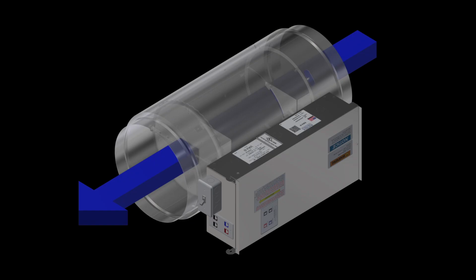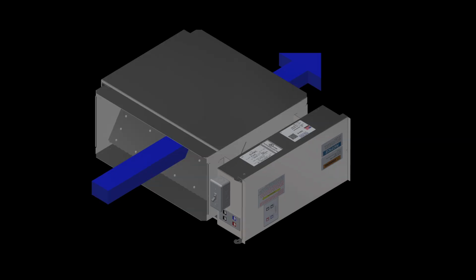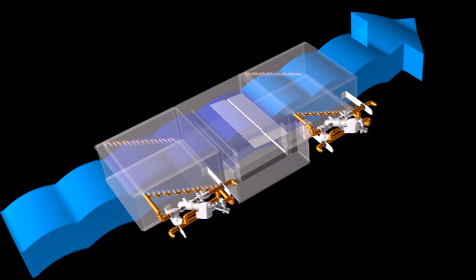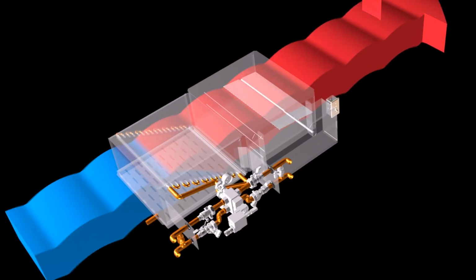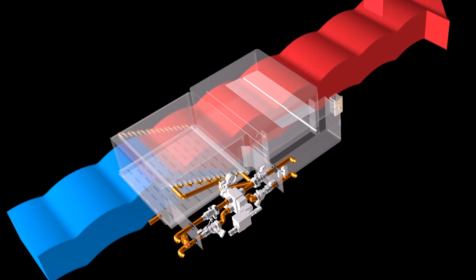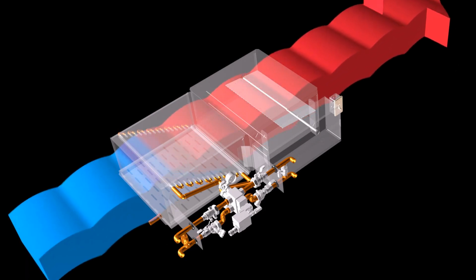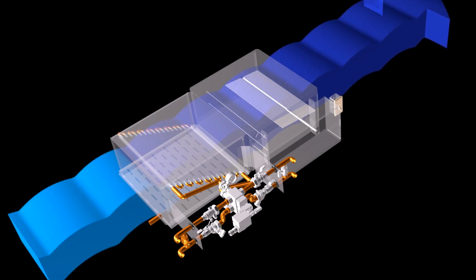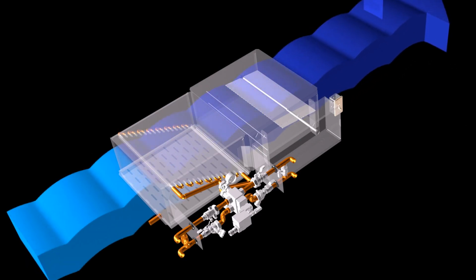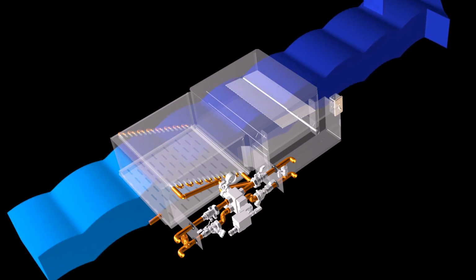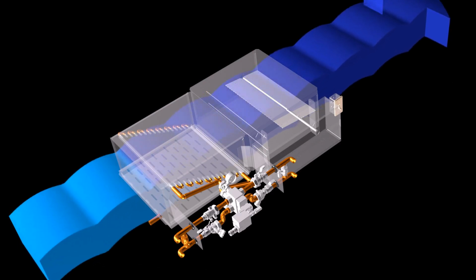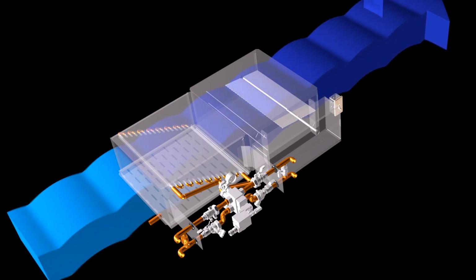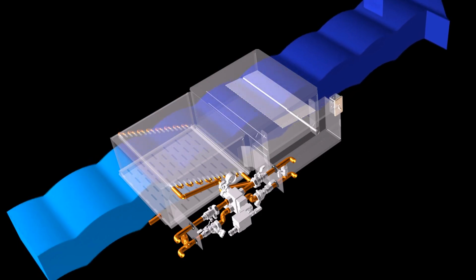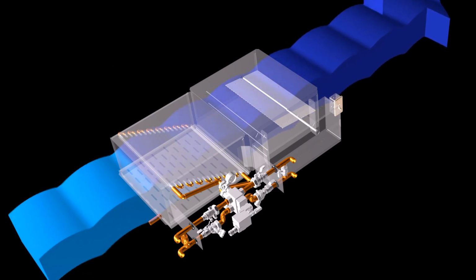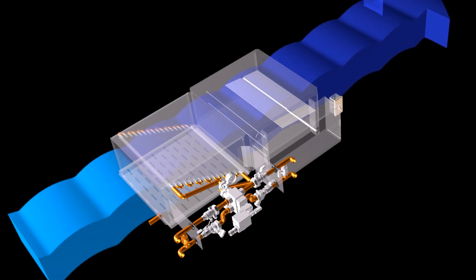The SAV is available in round with a non-clogging, maintenance-free, lab-grade, total pressure airflow sensor, and as a low-profile, cooling-only rectangular unit. The SAV is also available with an optional upstream, low-profile, factory pre-piped hydronic coil with factory preset pressure-independent control valve or electric heat for uniform airflow across the coil. The larger low-profile upstream surface area coil results in superior heat transfer, lower air pressure drop, with the ability to use lower entering water temperatures with less GPM, thus saving additional pump, fan, and boiler energy, including accurate airside BTUH monitoring with temperature reset sequence and accurate discharge air temperature readings.